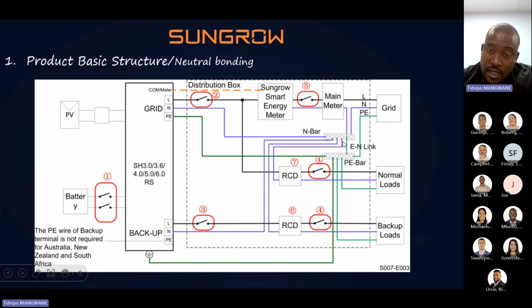So that tells us that neutral and ground are common in this scenario. This is after the inverter. So we avoid any break between the neutral and the grid side. In most cases, if this is not done accordingly, the inverter will shut down and restart again. So make sure that they go through this wiring diagram and bond accordingly.